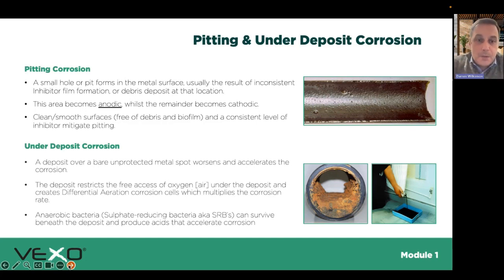At the same time, we have under deposit corrosion. As you can see in the bottom left picture, deposits settle out in a low flow area, or the flow rates encourage things to settle out, like you see there on the radiator. And what happens is below the deposits we have a lot less free oxygen available, and above the deposits there's a higher level of oxygen, and so that creates an electrochemical reaction that drives corrosion locally underneath, hence under deposit corrosion. So again, it's important that from the get-go we do not have any deposits that would like to settle out in the system. So we've got to keep the system chemically treated if required, or certainly chemically balanced, and prevent any suspended solids from circulating.